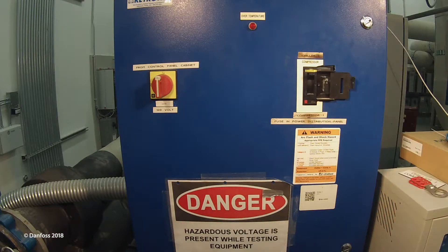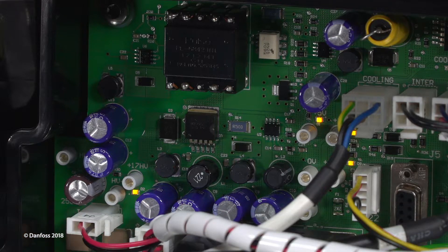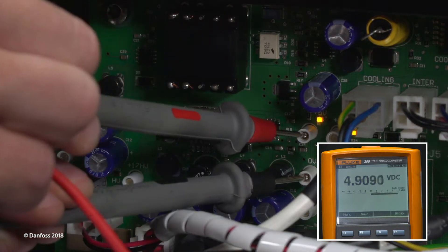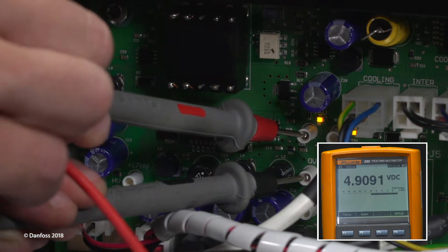Reinstall the PWM output cables. Apply power to the compressor to determine if the PWM is draining energy. Verify the related test points on the backplane using a multimeter set for DC voltage measurements. Insert the leads to the positive 5 and 0 volt test points.